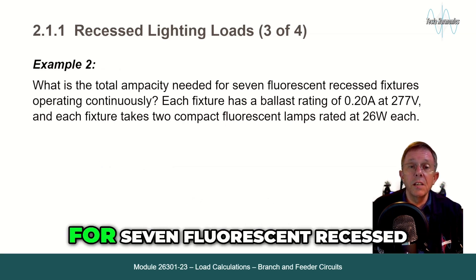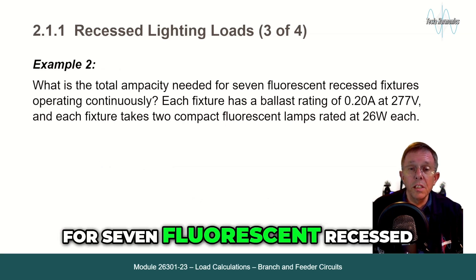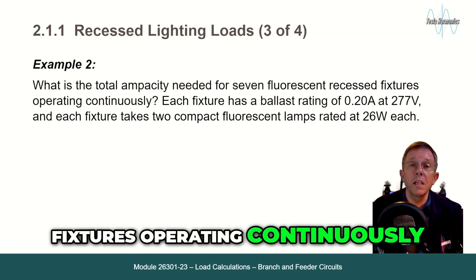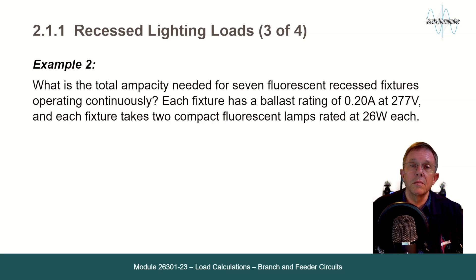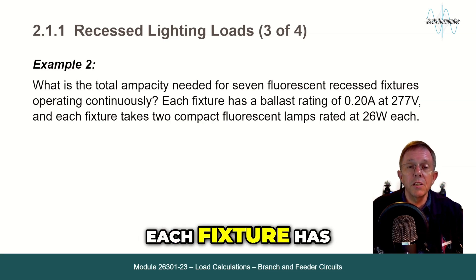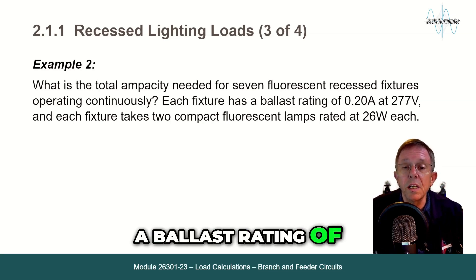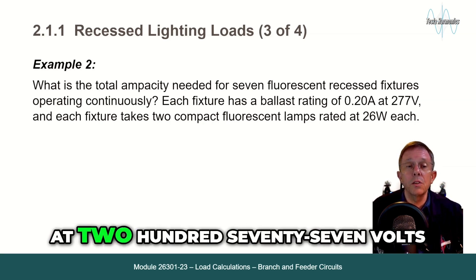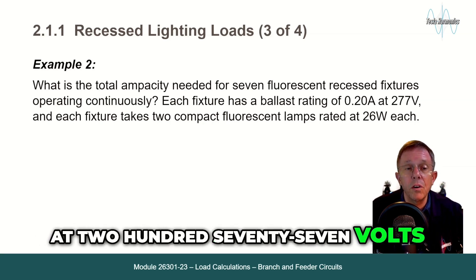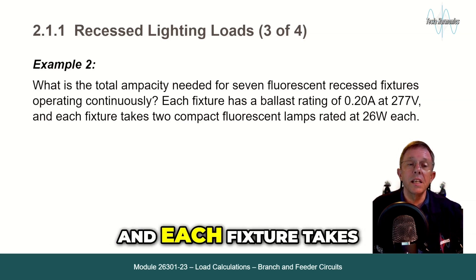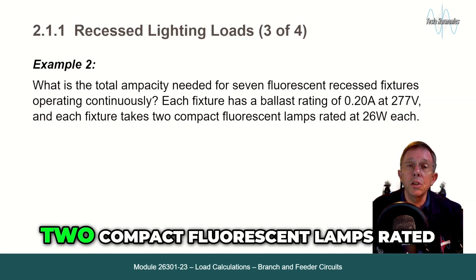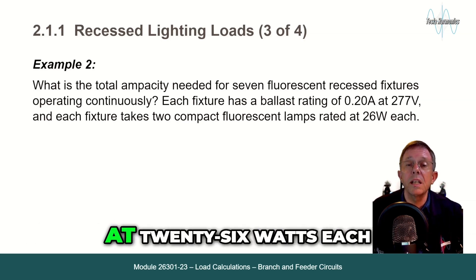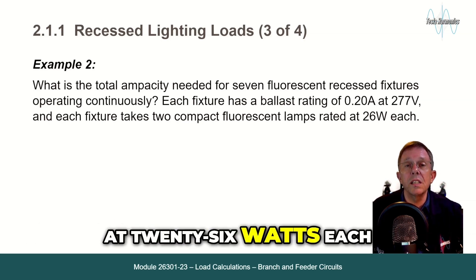What is the total ampacity needed for seven fluorescent recess fixtures operating continuously? Each fixture has a ballast rating of 0.20 amps at 277 volts, and each fixture takes two compact fluorescent lamps rated at 26 watts each.